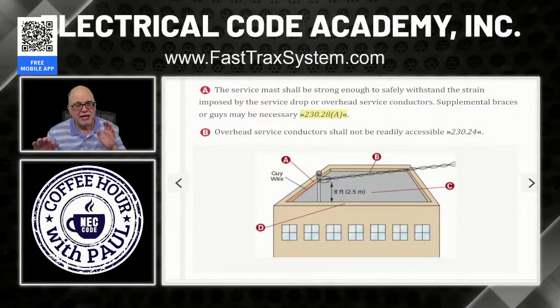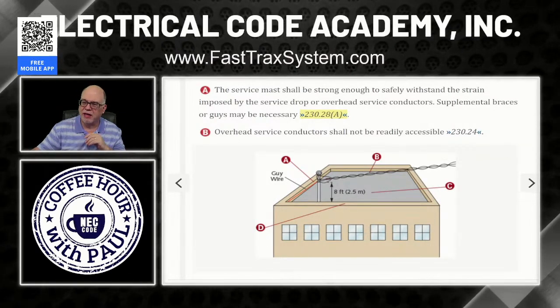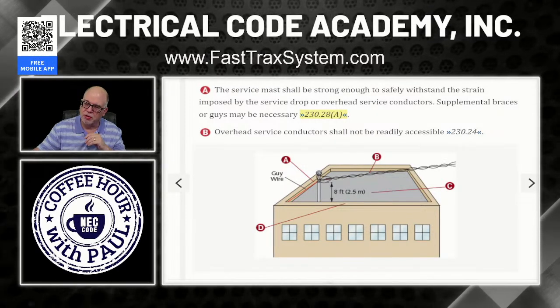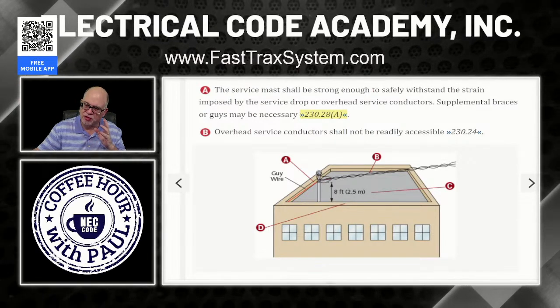Let me go back to it real quick. I just can't help it because I don't do the illustrations, even though they're great. I always like to bring things out. Anybody notice something here kind of weird? Yeah, notice that the service conductors run through the building. They're supposed to be on the outside of the building. Okay, you know, can't have service conductors running into the building.